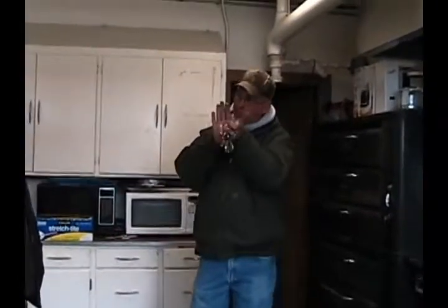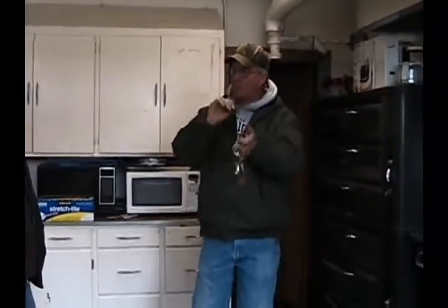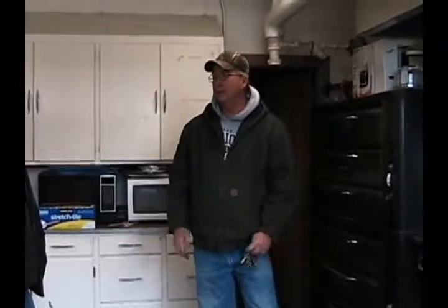It's going to have to be braced back up because it's so high. You have to run ties back. And I suggested, why don't you get rid of the oil tank, run the gas, it's high efficiency, get rid of the whole chimney, because they don't use the fireplace. Yeah. And so that's what they did. They vented it out the side, they ran the line in, they got a high efficiency gas furnace in there. Oh, okay. Nice job matching the slate in, because you can't even tell it's done. Yeah, right. It's on that side.